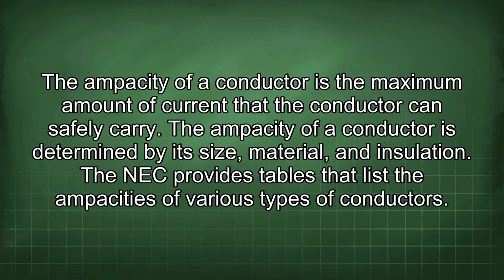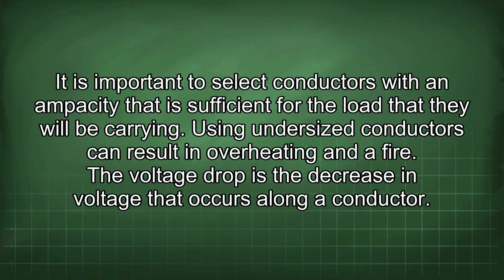The ampacity of a conductor is the maximum amount of current that the conductor can safely carry. The ampacity of a conductor is determined by its size, material, and insulation. The NEC provides tables that list the ampacities of various types of conductors. It is important to select conductors with an ampacity that is sufficient for the load that they will be carrying. Using undersized conductors can result in overheating and a fire.